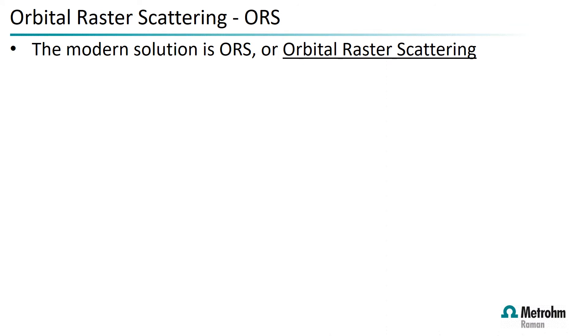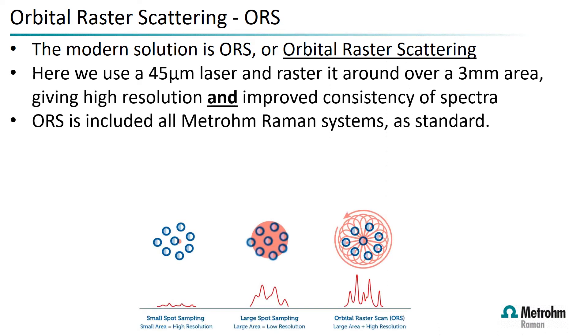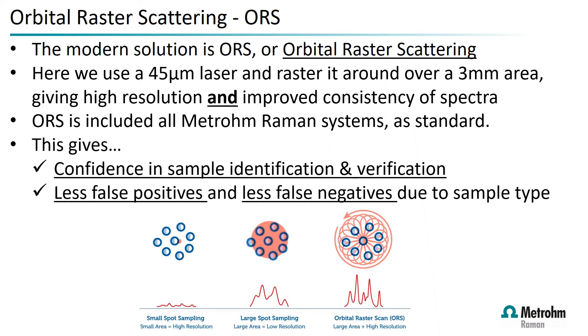The modern solution is a technique called ORS — also known as orbital raster scanning. Using a 45-micron laser, we raster it over a three-millimeter area by moving the laser with a mirror. This ensures we cover all particulates using our small spot size. This technique is included as standard on all Metrohm systems and provides confidence in sample identification and verification, resulting in fewer false positives and false negatives.